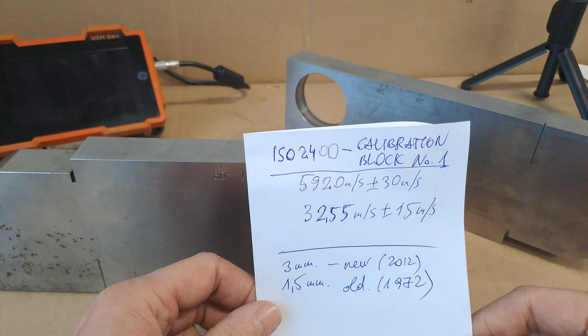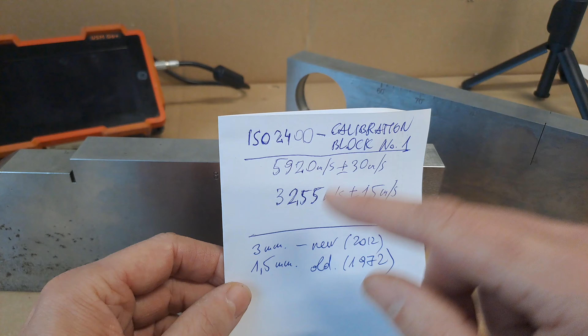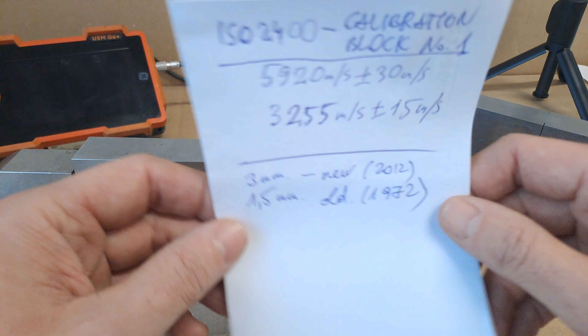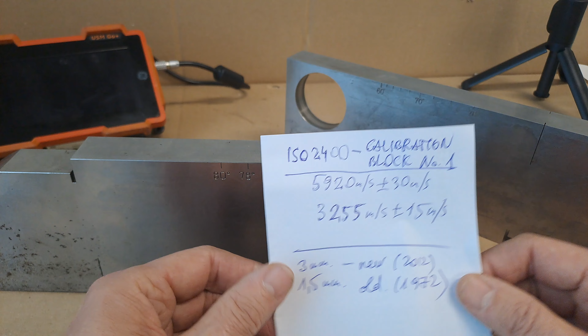So that's a good block, that's the newer one. That's the short one. Both are good, but the older one is with this smaller hole. The newer one, according to the standard, has a 3 millimeter hole. Everything else is the same. That's the standard block number 1, or V1.